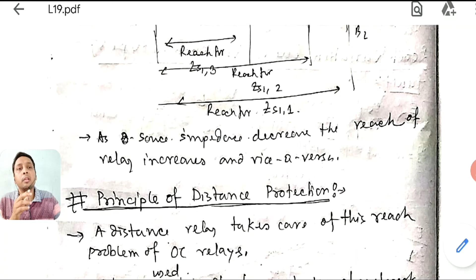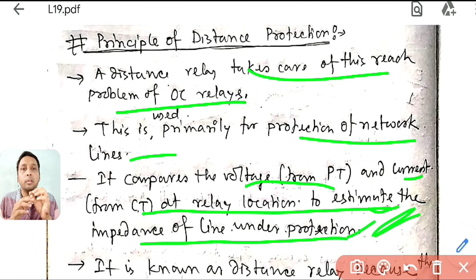Now what is the principle of the distance relay? The distance relay takes care of this reach problem, because here the reach is fixed. This is used primarily for the protection of network lines, that is your transmission line. So it compares a PT and a CT signal, so that at the relay location it estimates what is the Z. So it will sense this CT-PT to have some idea about Z.